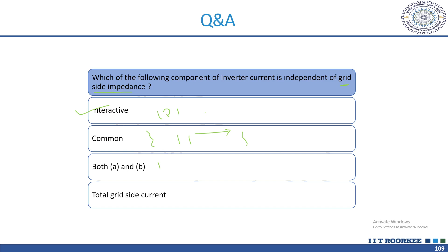No, it's grid side impedance. Basically, the common current is the one flowing out of this. Remember this is for parallel operation of inverters, say inverter one and inverter two. The common current which flows out will depend upon the grid side impedance, but the interactive current flowing between these two inverters will be independent of the grid side impedance. So it is basically the interactive current.